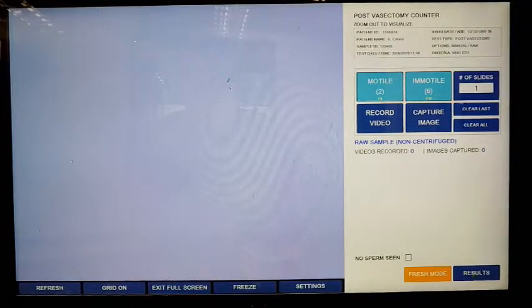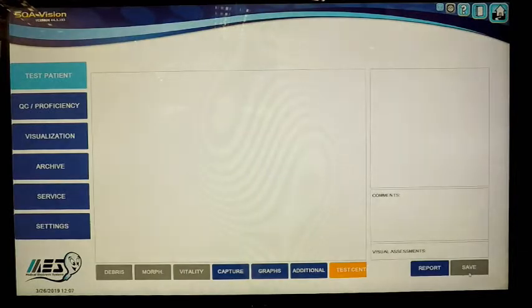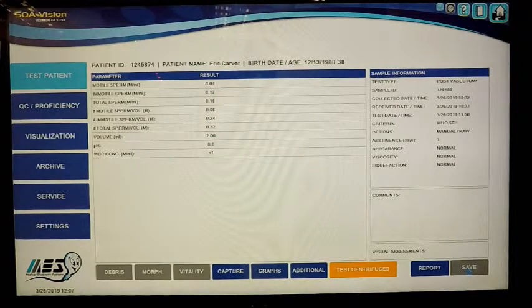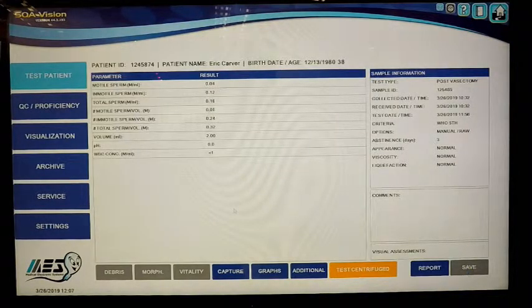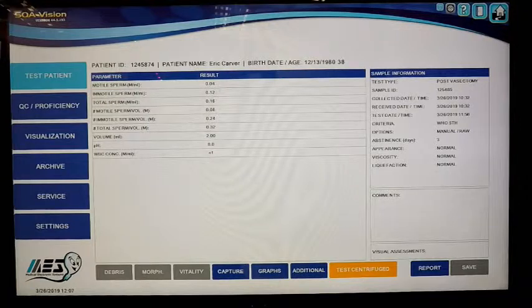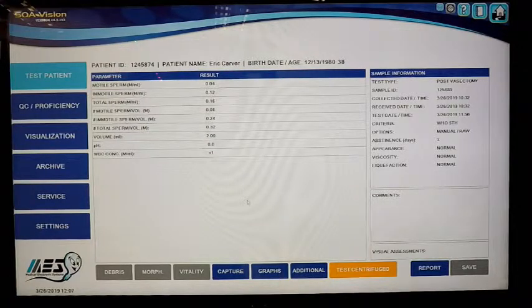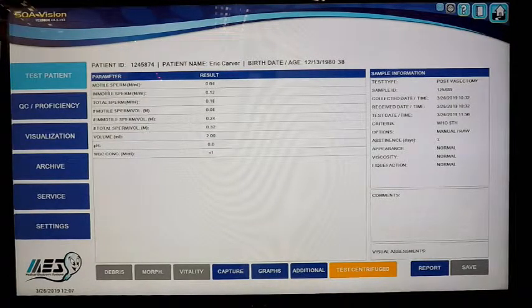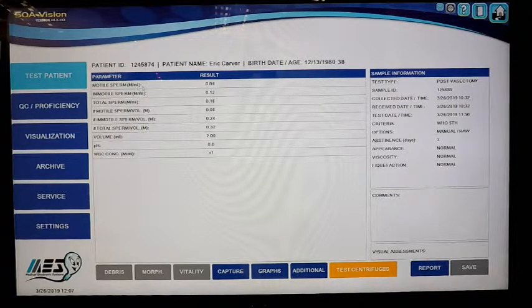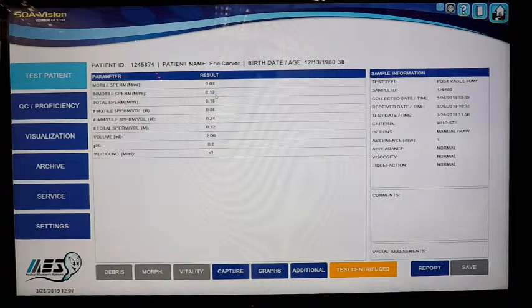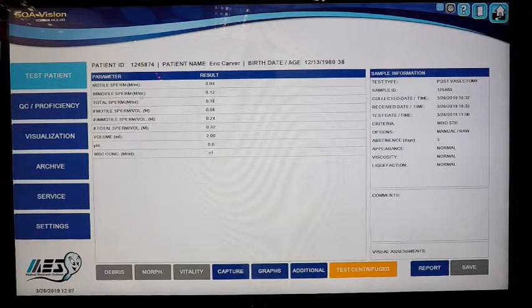You did have the option to run another slide if you wanted 100 fields of view. That'll drop the sensitivity even further. So you can see here you get quantitative results using the workflow of the Vision. You're going to get motile sperm in millions per ml, immotile sperm in millions per ml, and also totals for the entire sample volume.